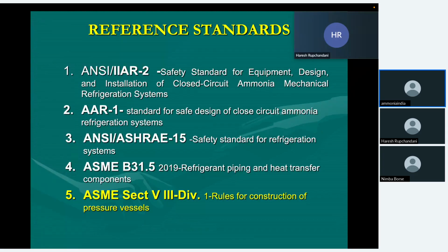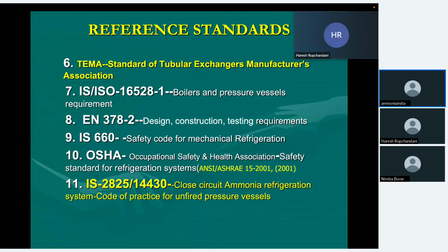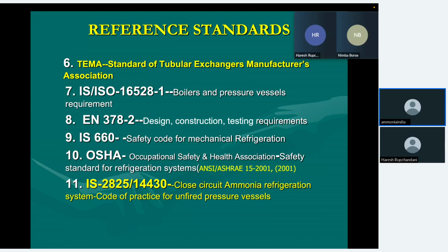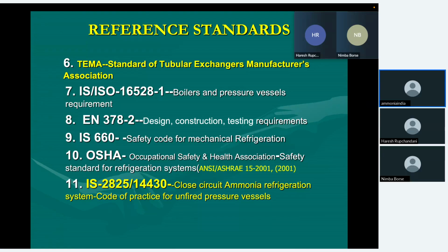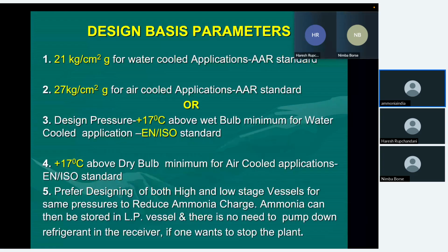We have initially indicated all these standards which are used in the design of pressure vessels. I'm not going to read all the standards, but the most important standard is ASME Section 8 Division 1, which is the rules for construction of pressure vessels. This presentation will be available on our website, so you can see all these standards. The next important standard is the TEMA standard, Tubular Exchanger Manufacturers Association, and of course our IS standard 2825, closed circuit ammonia refrigeration system, code of practice for unfired pressure vessels. So these are the three major standards.